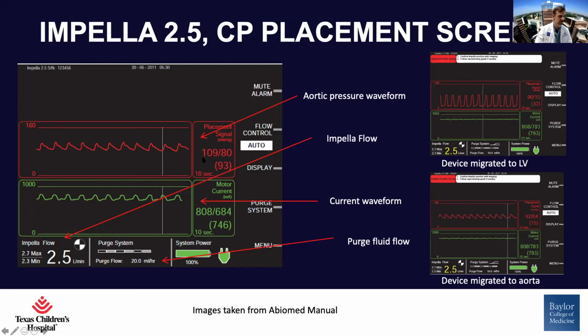So it is a second source of your arterial blood pressure. It also monitors the motor current, so the amount of energy used to drive the rotations per minute of the device. Typically, you should see a pulsatile waveform on both of these screens. The reason I mentioned that this is a really attractive feature is that if there is any change in these parameters, you can detect when the device is not in the right position. For example, if the device migrates into the left ventricle, as you can see in the figure in the right upper corner, the arterial pressure tracing will be indicative of left ventricular pressures, with normal systolic pressures but low diastolic pressures. At the same time, we'll see a change in the motor current, which will become non-pulsatile.